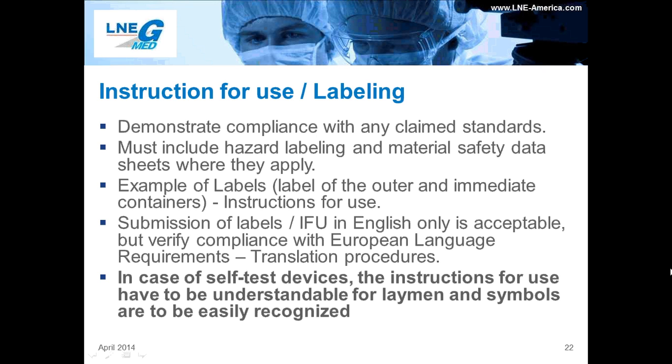Of course, the instructions for use must be provided to the end user according to the European language requirements. During the review, we will check to make sure that there are provisions to provide the IFU in the language of the country the product is being sold in, and this can be the actual translated IFU or a translation procedure with requirement to provide instructions in the appropriate language. In the latter case, it's perfectly acceptable to include the IFU in English only. For self-test devices, it's important to remember that the instructions for use have to be understandable by laymen and that the symbols have to be easily recognized.